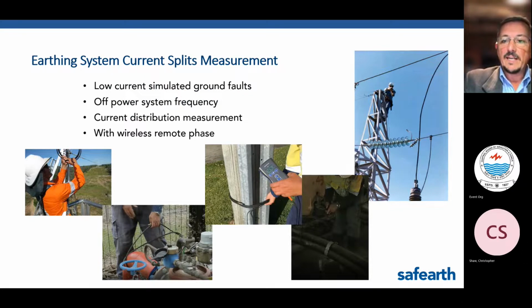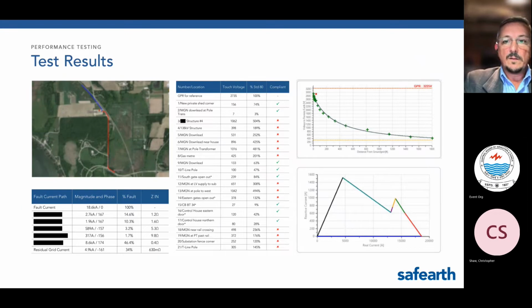When these currents are correctly summed, it can allow a very good estimate of the actual grid resistance and of the other component impedances. The results of performance testing can be very helpful in demonstrating safety and compliance, and they can help focus any remedial work where it is most needed. Of course, to be truly accurate, measurements must include magnitude and phase, and this is true for current in particular.